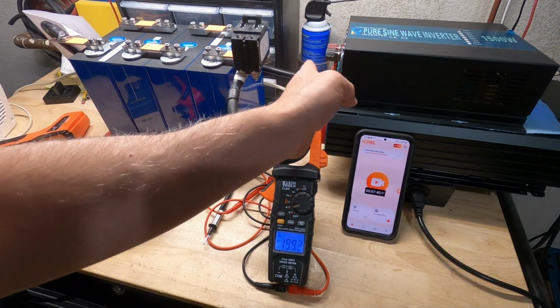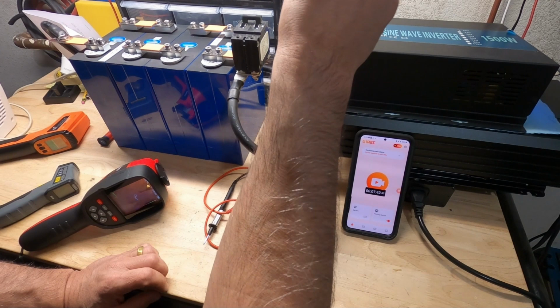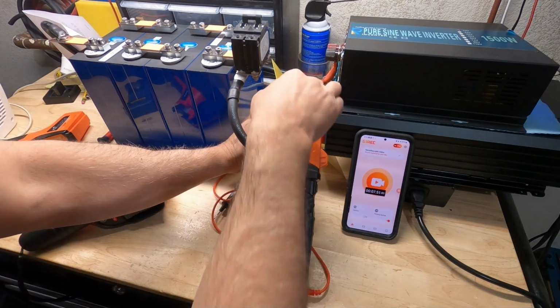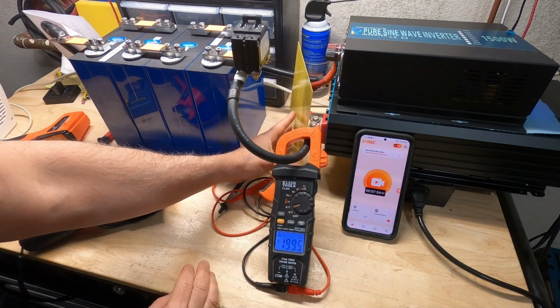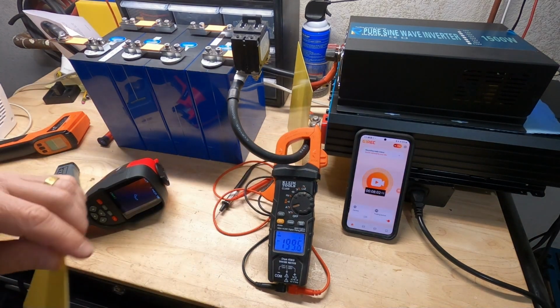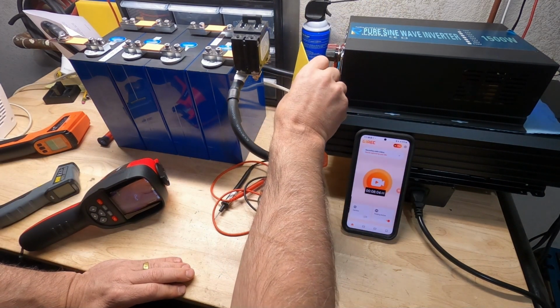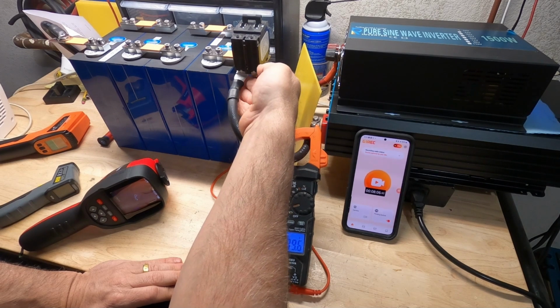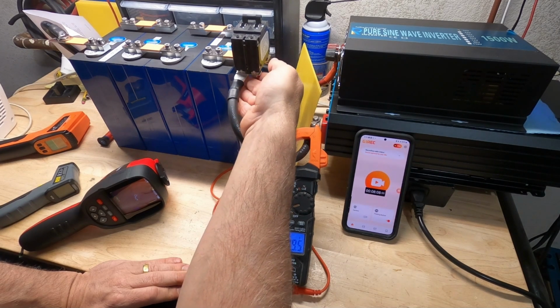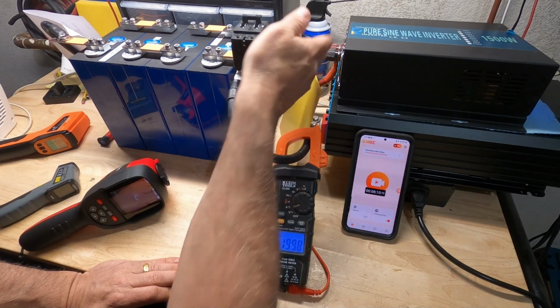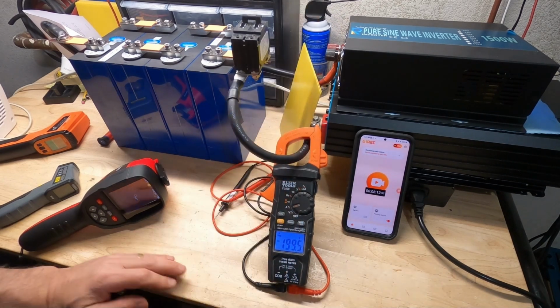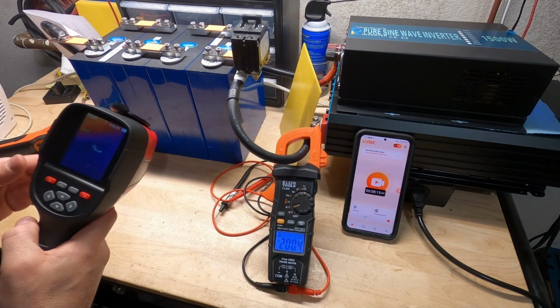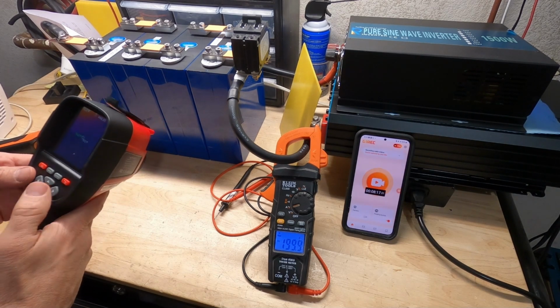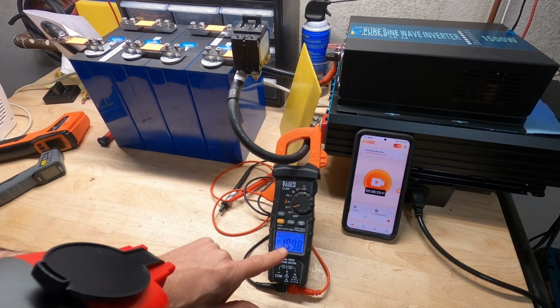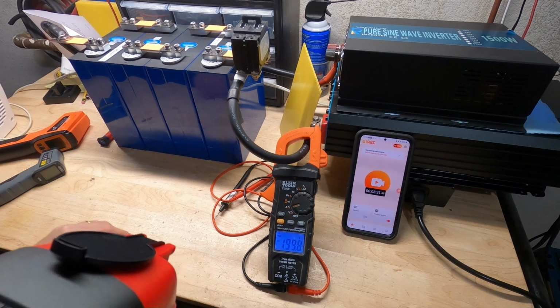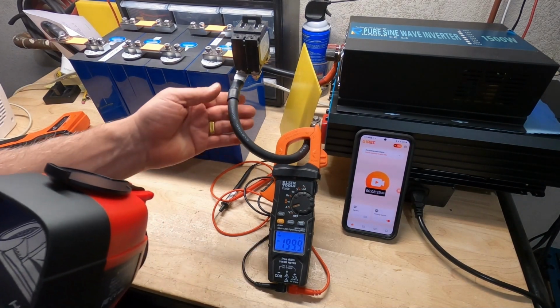Okay, so the fan's kind of blowing on the breaker here. We don't want the fan to be cooling that down. Can't have anything affecting the test here. We're pushing up on 8 minutes now. And the terminals on the breaker are, yeah, they're hot to the touch. You can touch them for maybe ooh, not that one. A couple seconds there. Let's check our temps. Still pushing 200 amps on the meter there.